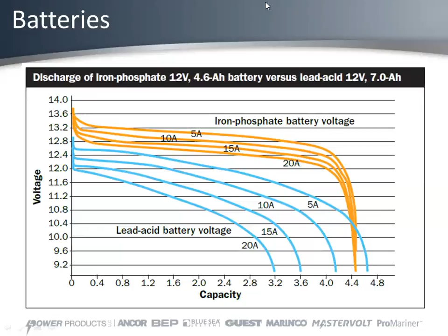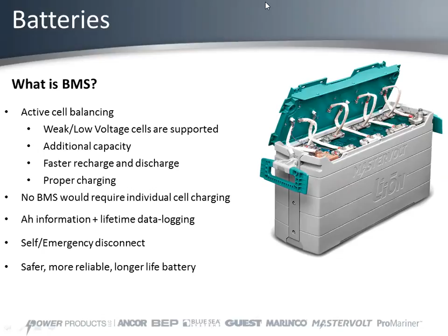Do you have battery chargers with the battery management system built in, or must it be separate? Nope, actually in our battery the BMS is built into the battery itself. What you see here, this part, is the BMS system. It sits in an IP65 enclosure, mounted on the battery. That's actually very unique, because most other lithium manufacturers have it as an external device, but we build it into the battery. So even if you build a bank out of multiple batteries, each battery has its own BMS system.